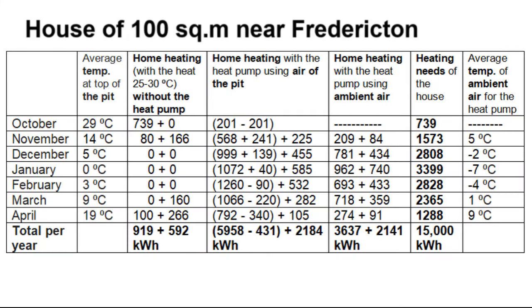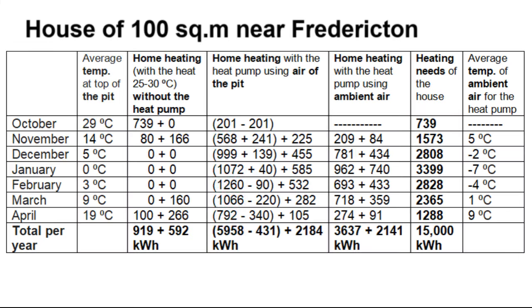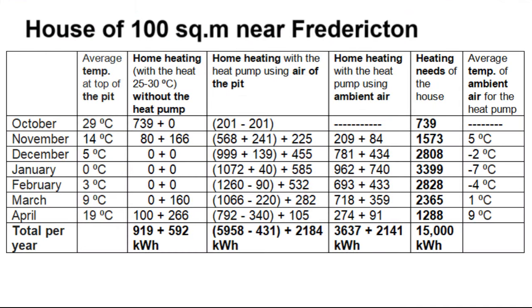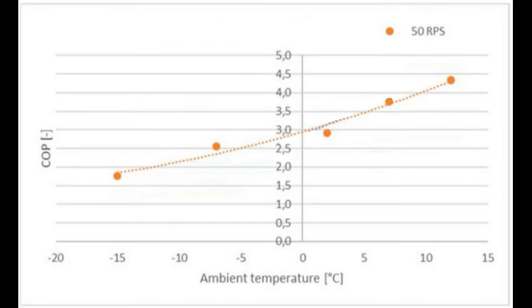This is the transfer of thermal energy from the solar panels into the pit when the temperature of the stones is less than 20 or 25 degrees Celsius. These kWh of heat are supplemented by heat leaks, heat flow from groundwater, accumulation of heat by the surrounding soil, and movements of heat due to changes in the temperature of the stones. These numbers are the electrical component of the heat pump, which converts this amount of solar heat with an efficiency based on this temperature according to the graph of an air-to-air heat pump.